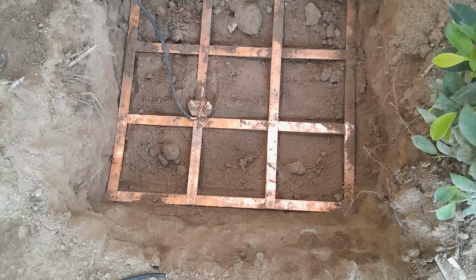I'm showing you some pictures on your screen. What we did, we supplemented the earth rod that was already there. We put in more earth rods. It wasn't done properly. We put in an earth mat, a new 16mm cable to the earth terminal in the distribution board. We bought a special earthing chemical enhancer. Okay, that's the black packet you can see on your screen, and that is a chemical mixture. When you put the earth mat in the ground and the earth rod, you mix that chemical in with the soil. Okay, and that helps to maintain a low resistance as well. Okay, it's a very good chemical product to use in your earthing installation.